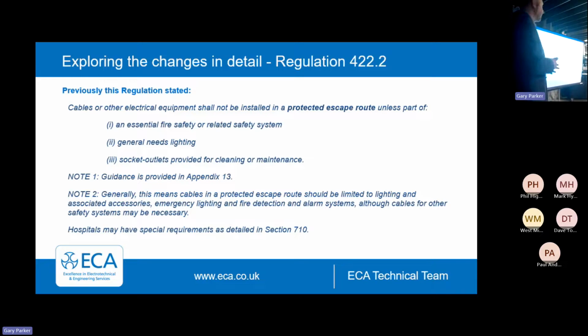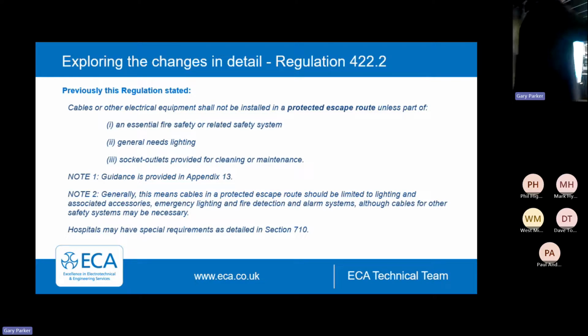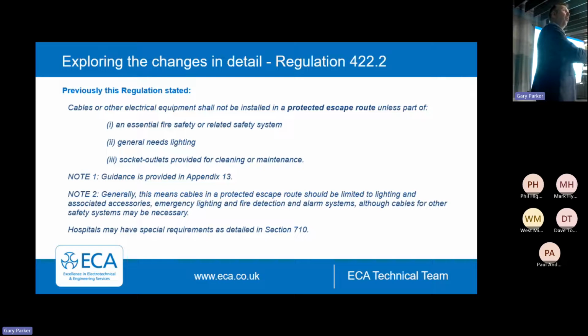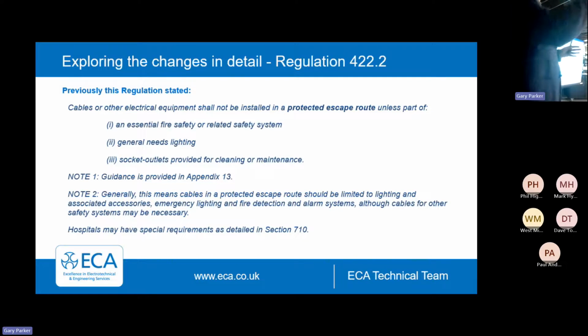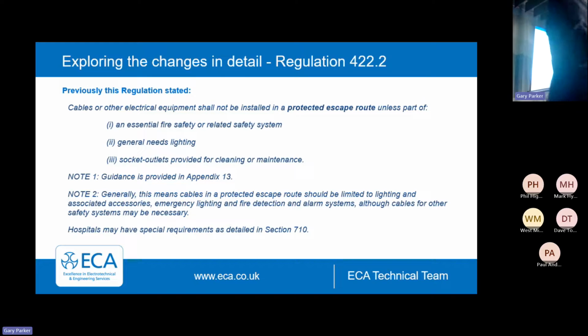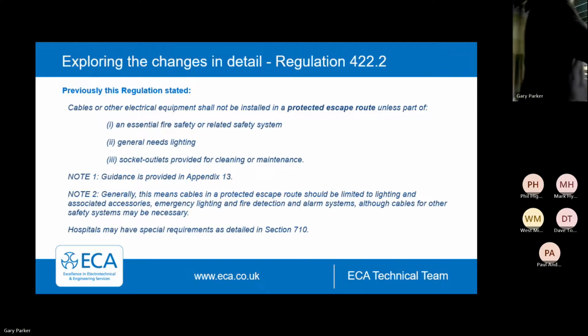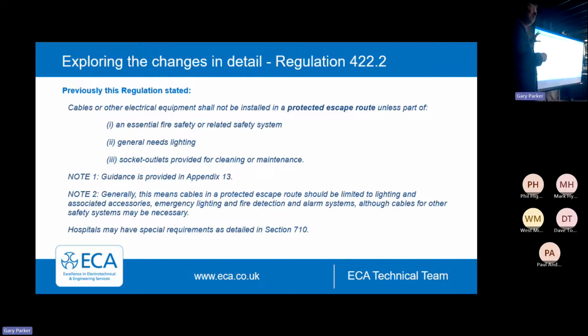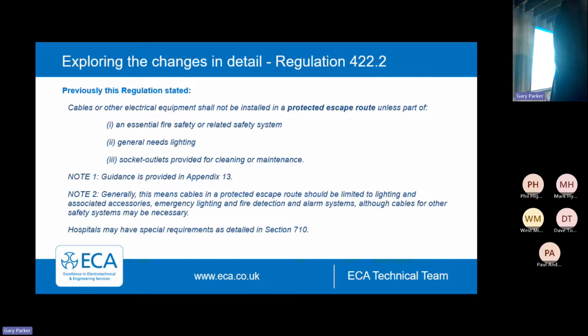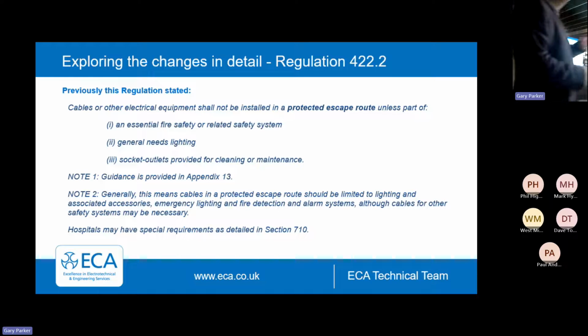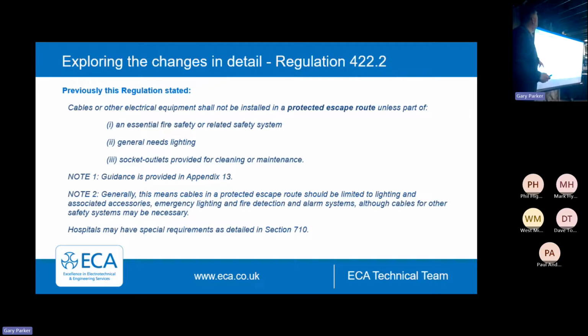The idea is quite nice. We've got an escape route that you try and get out, but then you've got a protected escape route, something designed to last 30, 60, or 90 minutes, whatever the fire engineer or architect specifies. Within that protected escape route, essentially this is saying don't add to the fire load. This section of the building is designed to be inherently fire sterile. Don't go putting boards, cables, and other things in it that don't need to be there. Only put the essentials - general need lighting, socket outlet for cleaning, etc.